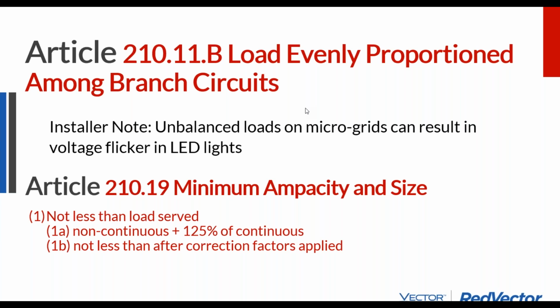It's not really a positive and negative like you have on DC, but it's perfectly out of sync phases alternating between positive and negative, like mirror images of each other. They all connect to that common grounded neutral point. Both of them have their electrical voltages to ground.